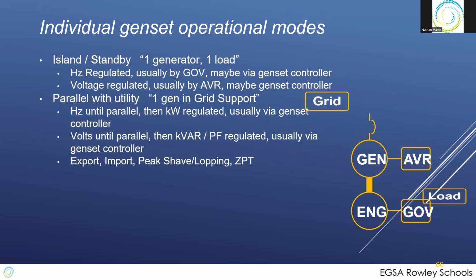One generator, one load. You can do one generator to the grid, and this becomes a generator in grid support mode or a KW regulated system. So until you parallel, it's frequency regulated, then you parallel with the grid, you switch over to KW regulated, and you say, put out so many KW. And it'll fuel up, put out so many KW. The VAR is controlled by the power factor or the VAR controller, which says increase excitation to maintain a certain level of VARs in the system.